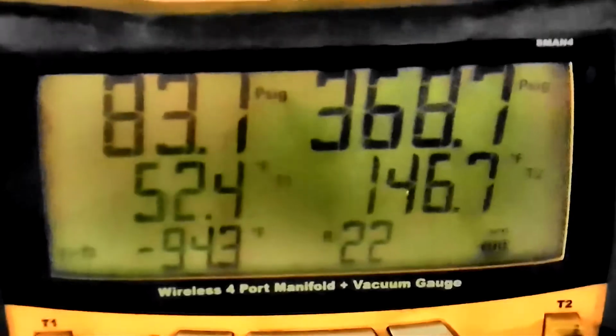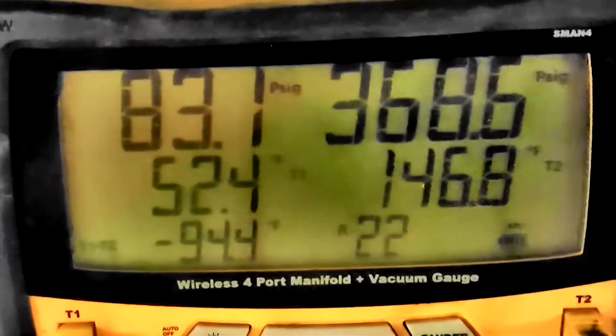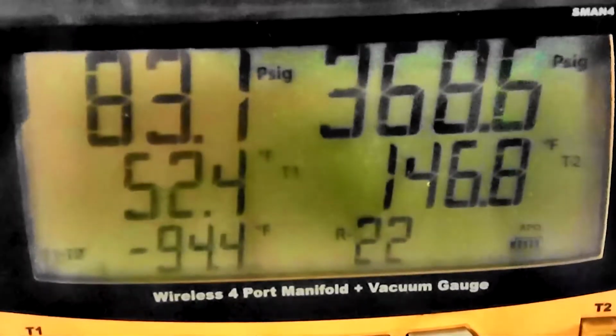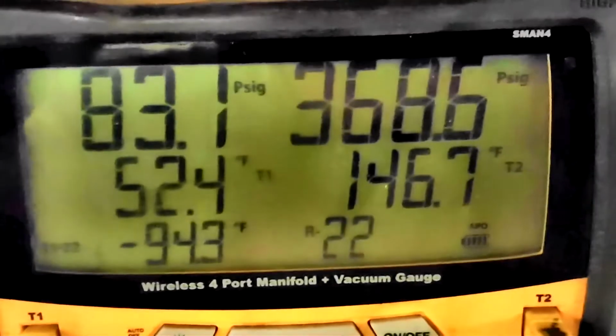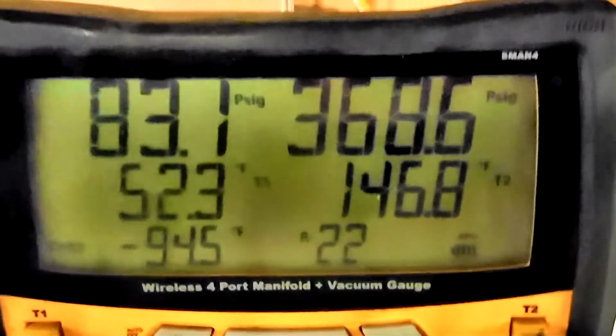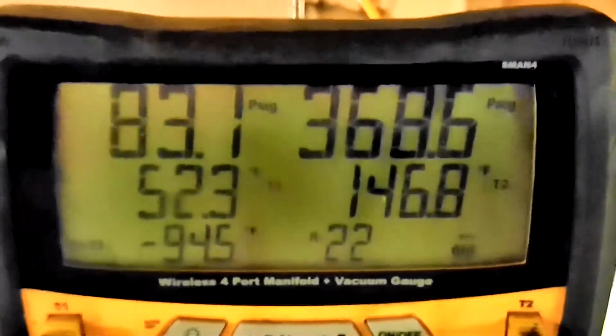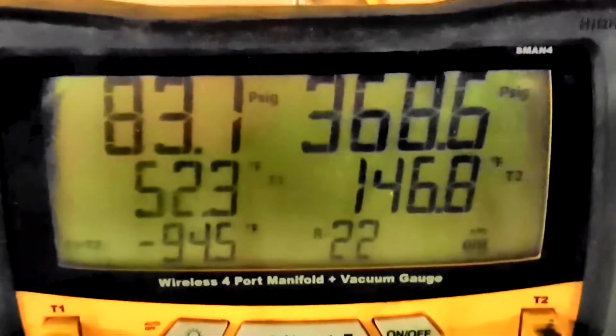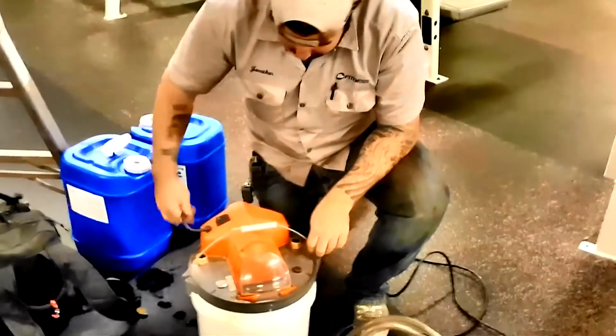In this video I'm going to be introducing how to descale a unit. So as you can see, the suction pressure is 83 psi, head pressure is 368 psi. At this point I have a thermocouple installed on the return water, which is water leaving the water source heat pump. The temperature in the water is 146.8 degrees leaving water temperature. Water coming in is 80 degrees.